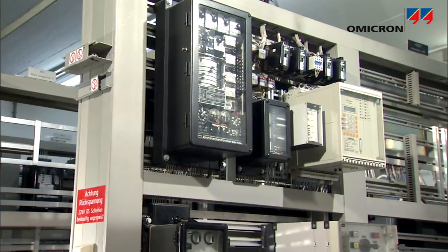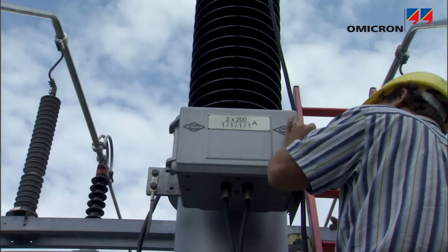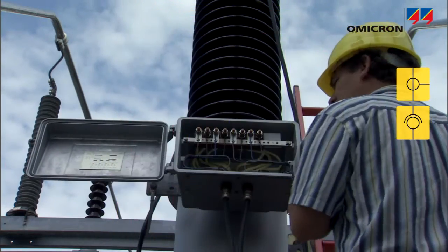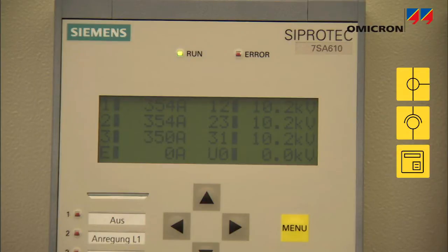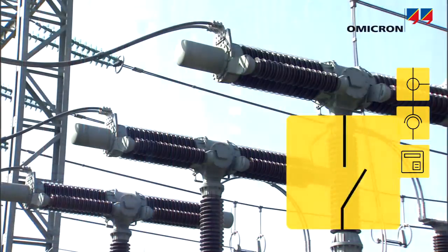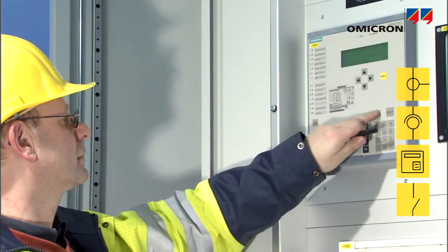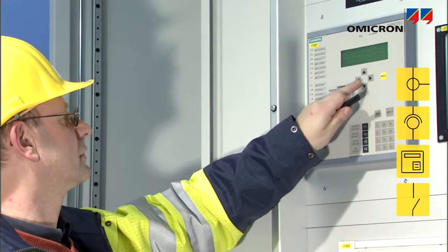Protection and control systems have to be integrated correctly in order for a substation or power plant to work reliably. All signals must be connected with the correct polarity from the instrument transformers to the automation units, meters, and protection relays, and from the relay's trip contacts to the circuit breakers. To assure the correct function of the protection system, each of its components is tested, as well as their interaction.